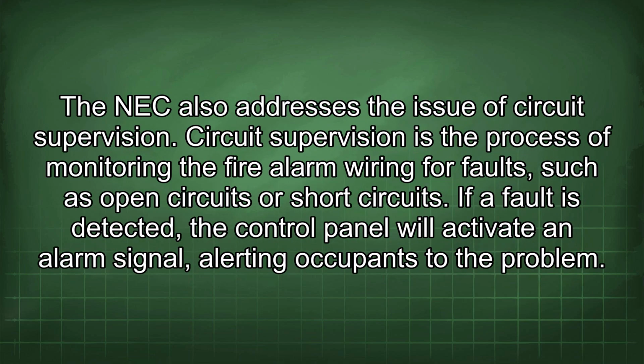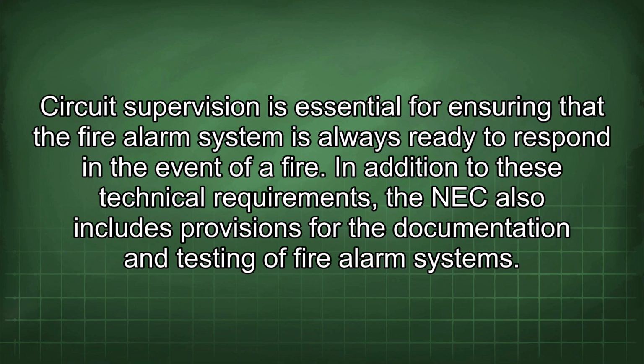The NEC also addresses the issue of circuit supervision. Circuit supervision is the process of monitoring the fire alarm wiring for faults such as open circuits or short circuits. If a fault is detected, the control panel will activate an alarm signal alerting occupants to the problem. Circuit supervision is essential for ensuring that the fire alarm system is always ready to respond in the event of a fire.